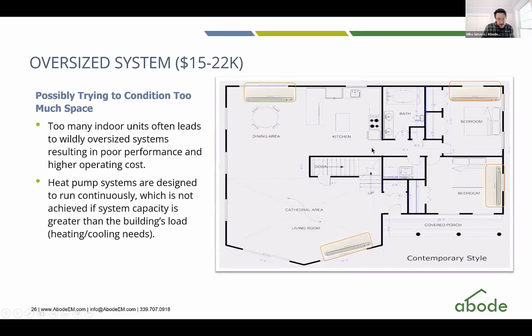We'll talk more about this concept throughout training, but here's the core concept over here. It's really easy to oversize a heat pump system when you're trying to put a ductless unit pretty much anywhere that you would have originally had a radiator or a register. And why this is a problem is because with heat pumps, they modulate, but they only modulate so much.